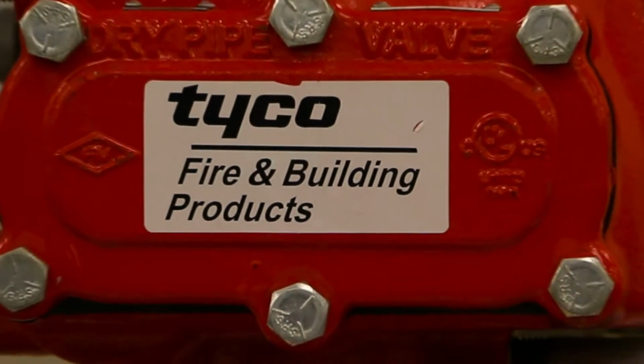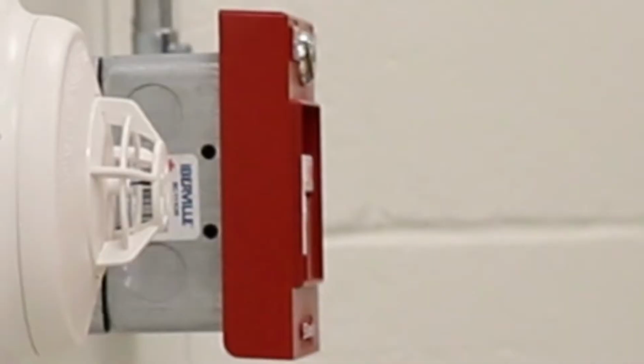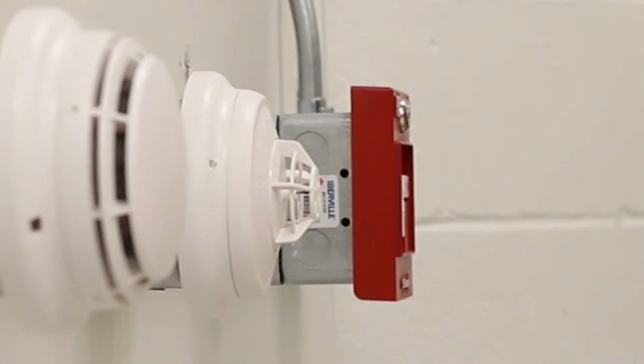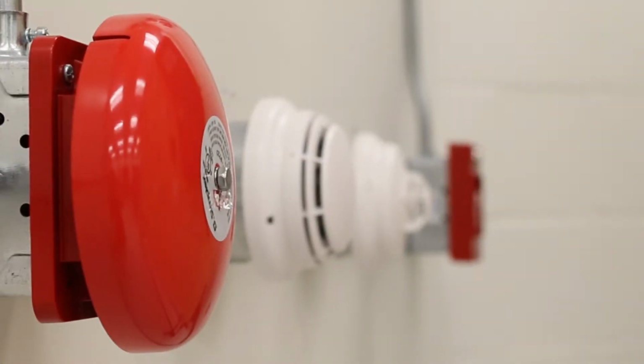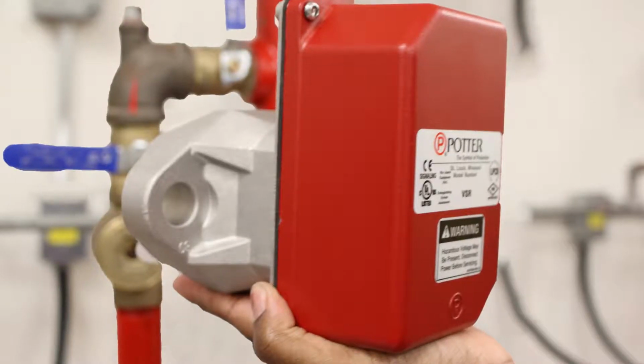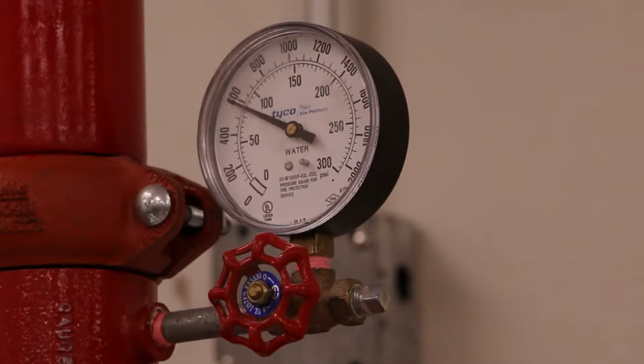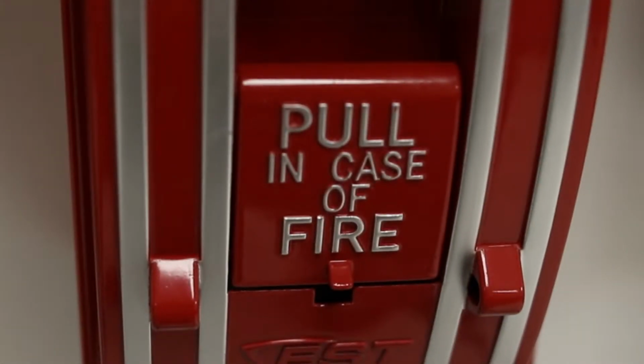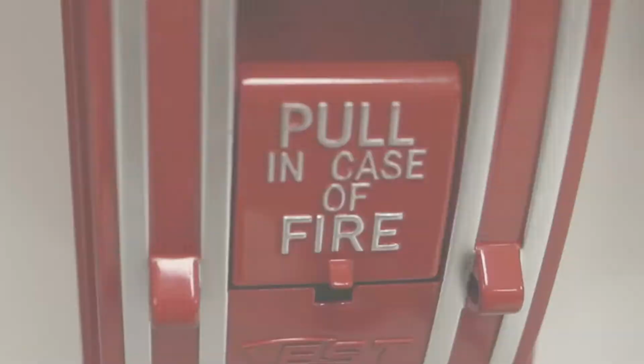Water flow is one of the most important things to test because it is what signals the activation of the fire alarm to make sure people will leave. It is important to make sure that not only the alarm works, but that the flow of the water is confirmed so that it can put out the fire. You do this by checking to see if the water flow actually causes the alarm switch to operate.